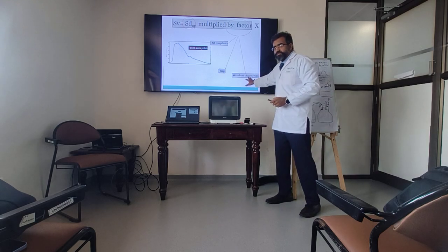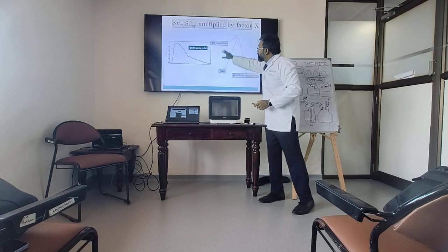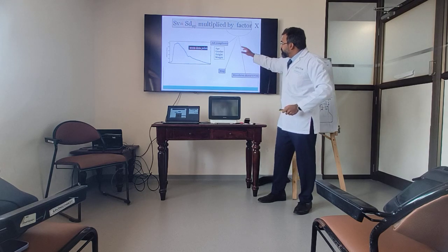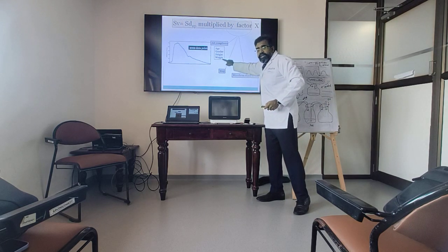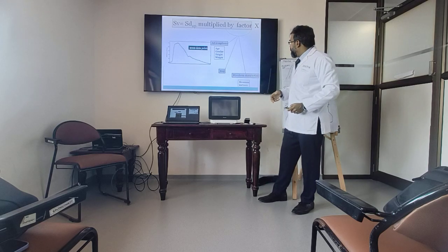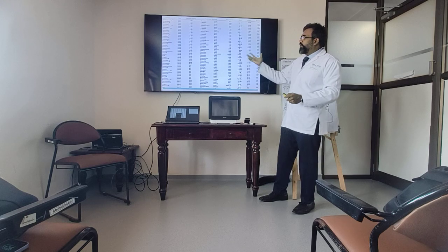It takes that waveform and looks at the mean arterial pressure, and then it looks at compliance, from where? From weight and height. With age, gender, height and weight, it gets the compliance, which it has to add into the system. Skewness and kurtosis are the waveform characteristics it looks at, and with that they find out cardiac output.